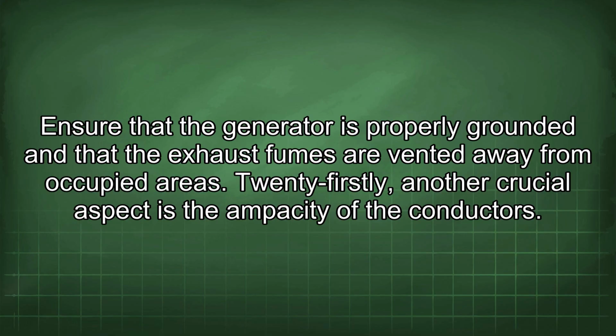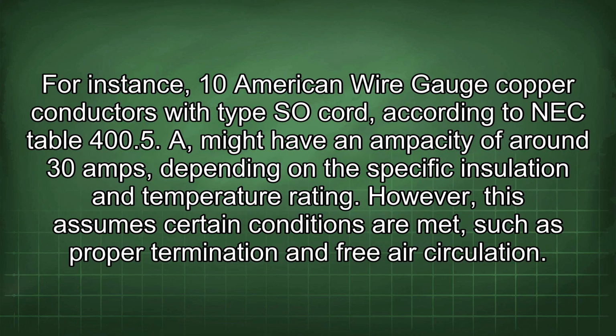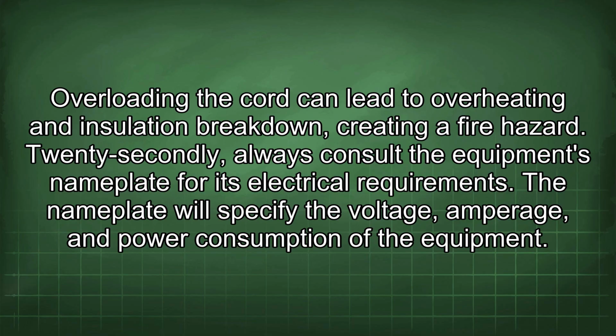21stly, another crucial aspect is the ampacity of the conductors. For instance, 10 American wire gauge copper conductors with type SO cord, according to NEC Table 400.5(A), might have an ampacity of around 30 amps, depending on the specific insulation and temperature rating. However, this assumes certain conditions are met, such as proper termination and free air circulation. Overloading the cord can lead to overheating and insulation breakdown, creating a fire hazard.